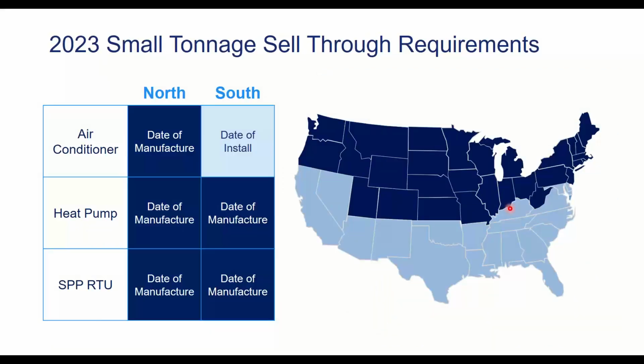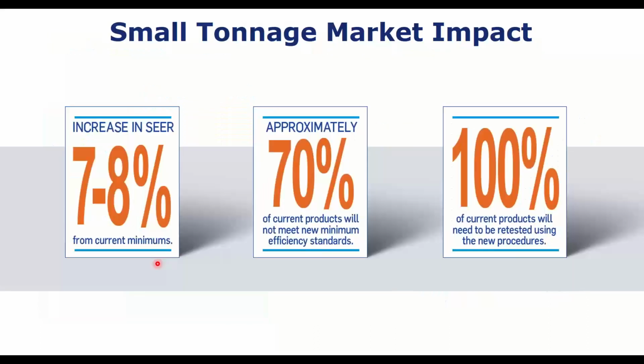Generally speaking, as I said, all the Department of Energy stuff is policed at the point of manufacture. So if something's made before the cutoff date, you can still install it the next year, right? Until your building code locally changes. One exception to that is AC and down south. Down there, it's based on the date of install. But since none of you guys live down there, it doesn't matter unless you retire and move down there, or semi-retire and move down there. If you retire, you don't care either. So for Illinois, Indiana, Wisconsin, Midwest, Kansas City, all of that, it's based on the date of manufacture for all of these things. You can still install it after the date, as long as it wasn't built after the date.